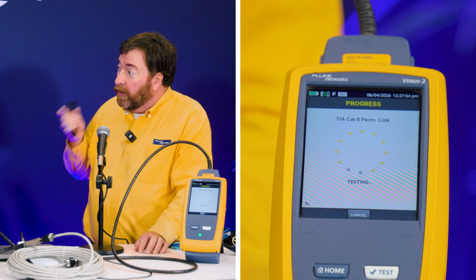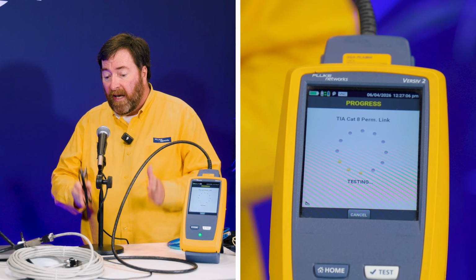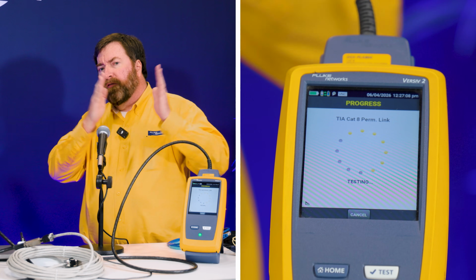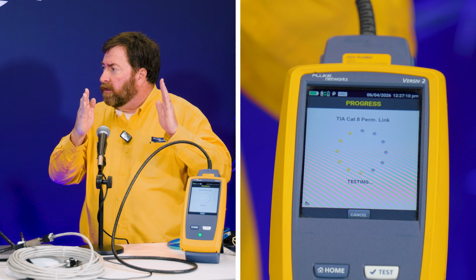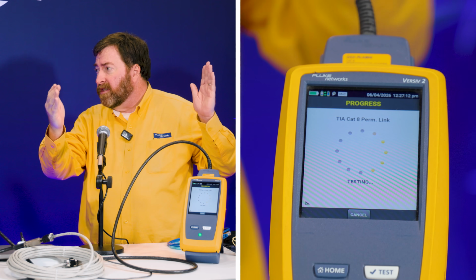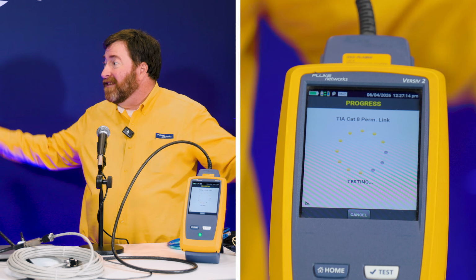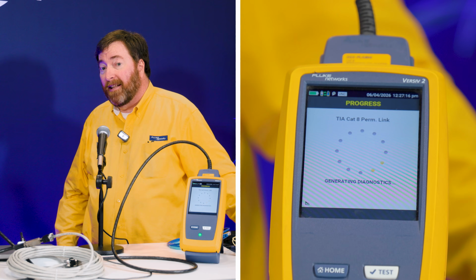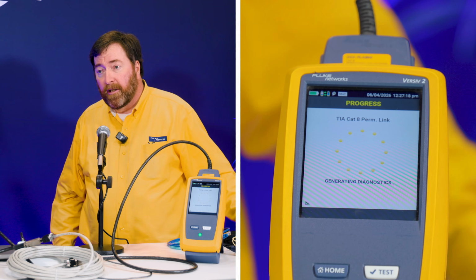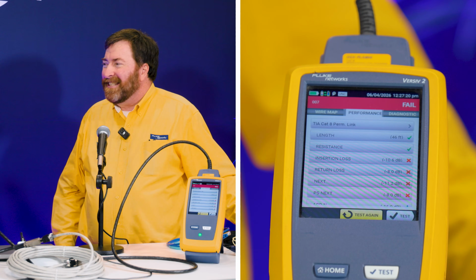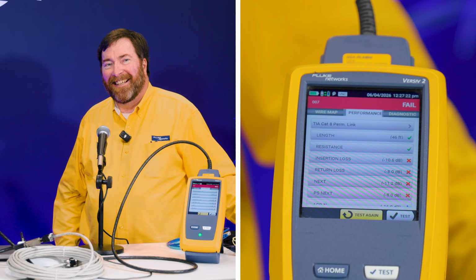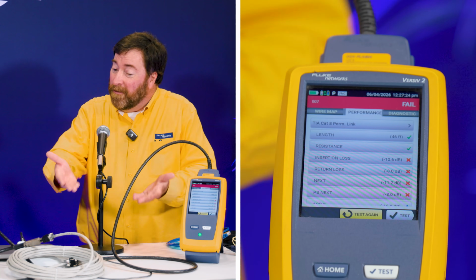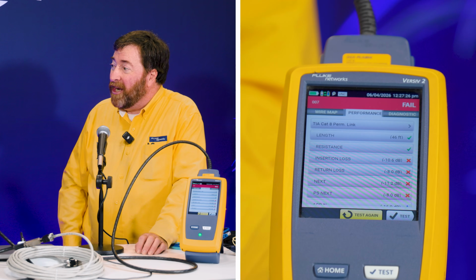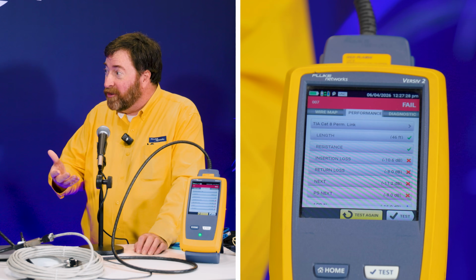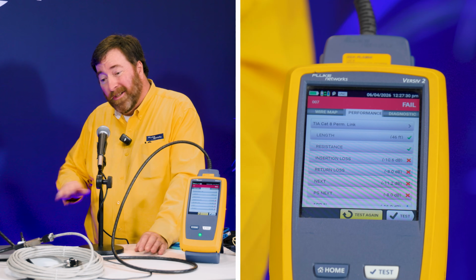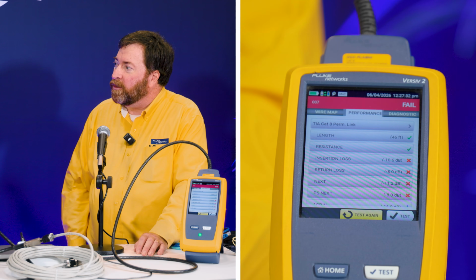Now, this test is going to take a little bit longer because our category 5E test measured to a frequency of 100 megahertz. Yep. Category 6 is 250, 6A is 500, and category 8 is 2 gigahertz. So that's a lot of space. It takes a little bit longer to run the test. And there you go. Yeah, that's not a good noise. So no, even if it said category 8 on the jacket, electrically under the jacket where the signal travels, where it matters, this one doesn't quite meet those requirements.